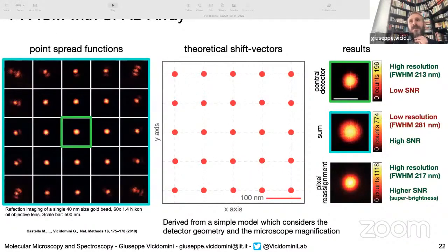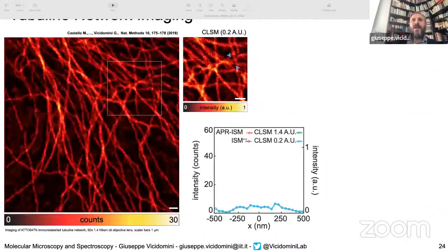And very important, you also collect most of the light from your sample. As you know, typically in a confocal microscope, you can also achieve high resolution, but you need to close the pinhole and thereby reject a lot of light. With such a system, called image scanning microscopy, you collect all the light because your detectors are in parallel collecting signal, and every element is acting as a pinhole, and then you can computationally reconstruct an image with high signal to noise ratio and with high spatial resolution.